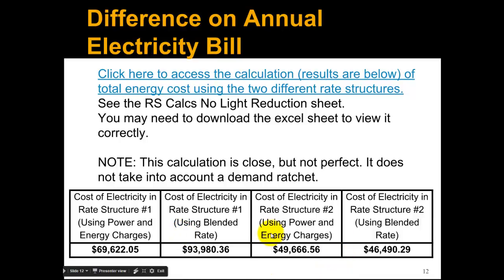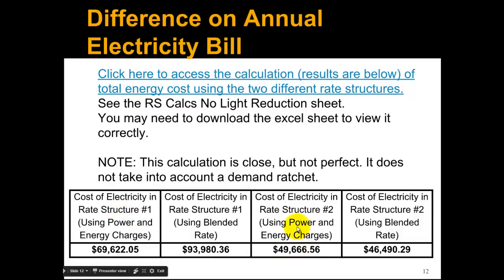Doing the same thing with rate structure number two, there's not as big of a difference with the blended rate, but in this case the blended rate is actually lower. That's why you always want to really use the power and energy charges and never the blended rate, because it can make a huge difference when you're evaluating whether or not to stay on one rate or another. The school actually did a really good change — their utility electric charges for the year were almost $70,000 under the first rate structure, and now they reduced it to $50,000. That's a $20,000 savings from just a phone call to the utility company.